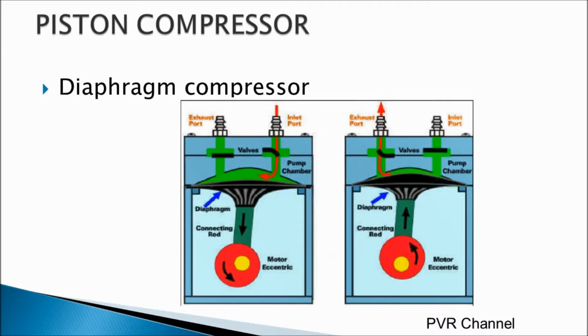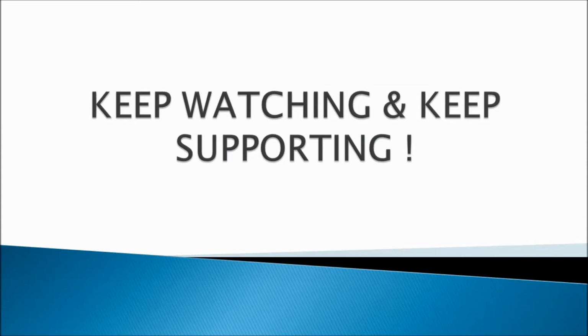Now this is a diaphragm compressor, and this diaphragm compressor has some special applications. Diaphragm compressors provide compressed air in the range of 3 to 5 bar only, totally free of oil, and are therefore widely used by the food, pharma and other similar industries. The diaphragm provides a change in the chamber volume. This allows air in during the downstroke and compression in the upstroke. Smaller types with a fractional HP electric motor and small reservoir make portable compressors possible, ideal for applications like spray painting.